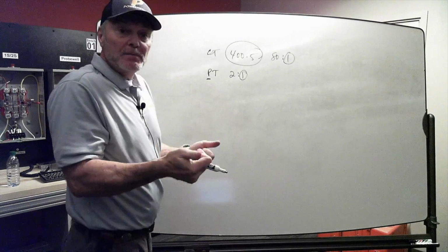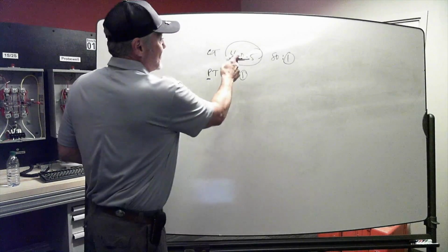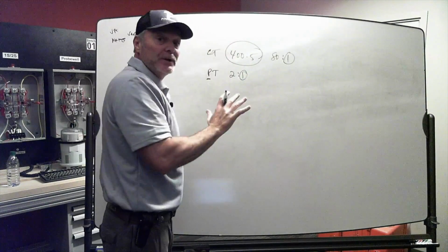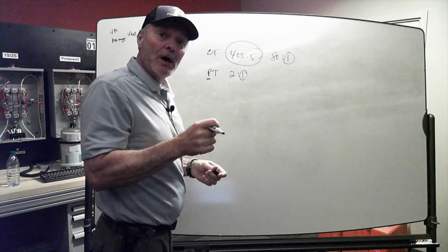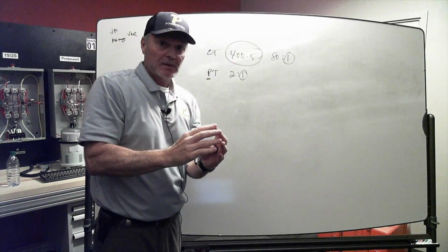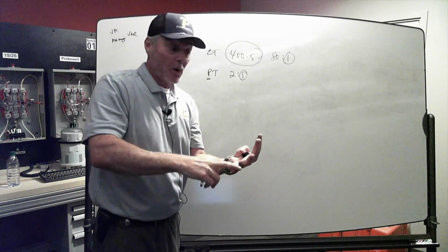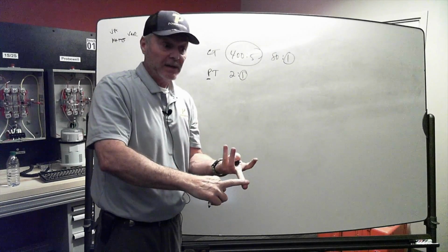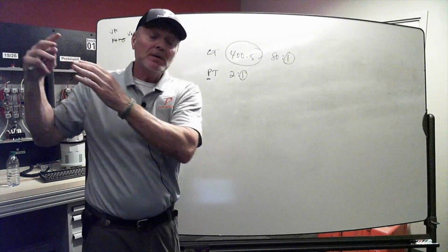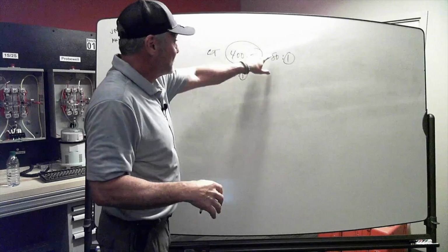You go out there and you measure it with your test equipment, and when you take the measurements, remember, it's been stepped down. So is that what you're really going to bill on, what you test? No. That's what the billing multipliers are for. You step it down so that you and I can do our work, take our measurements, and come up with our readings. But when you get ready to bill someone, you got to step it back up, so to speak. You got to crank the bill back up because we've stepped this down.